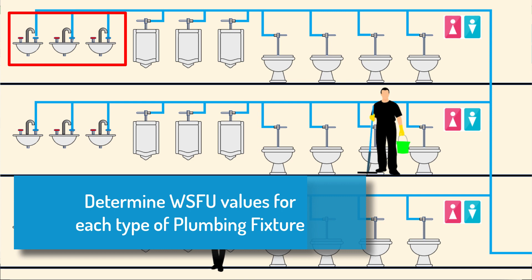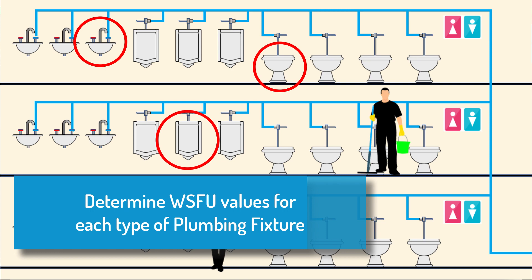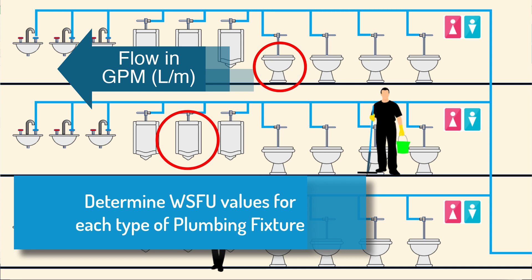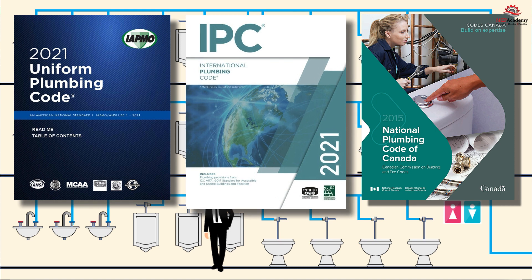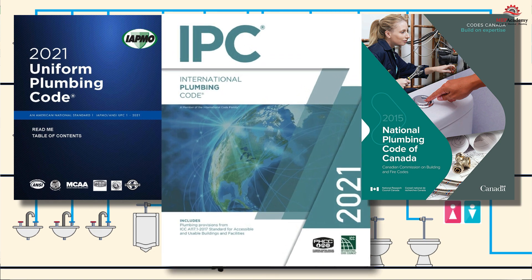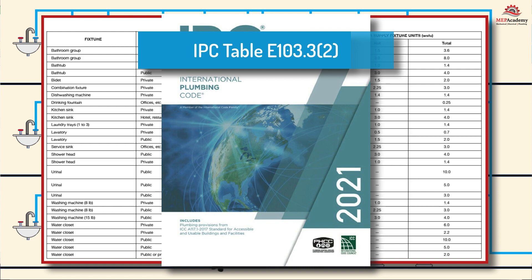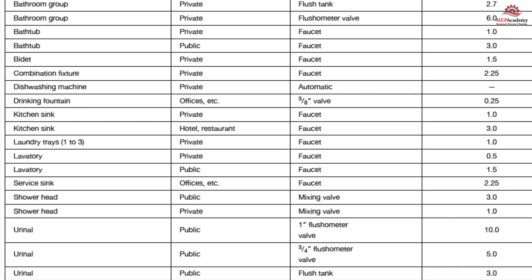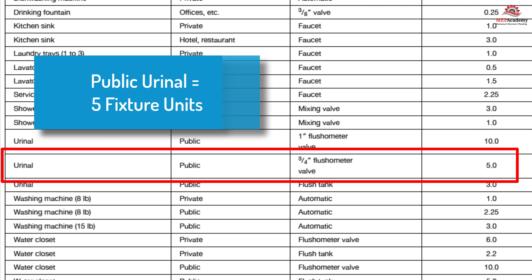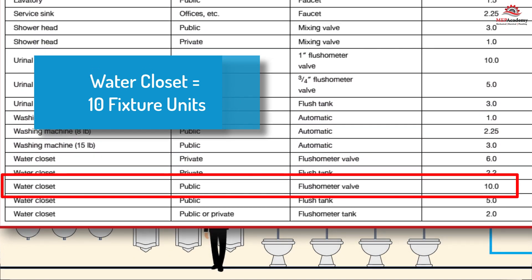Determine the water supply fixture unit value of each type of fixture. Water supply fixture units, or WSFU, is a measure of the flow rate of water through a specific fixture. The WSFU of a fixture can be found in the plumbing code or by consulting a plumbing engineer. Here we show several different codes and the various tables they use for fixture unit values. We use the 2021 International Plumbing Code Table E103.3.2, which shows that a public lavatory has 1.5 fixture units, a public urinal with a three-quarter inch flushometer valve has 5 fixture units, and a water closet with a flushometer valve has 10 fixture units.